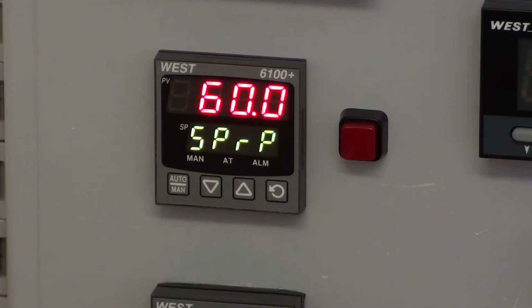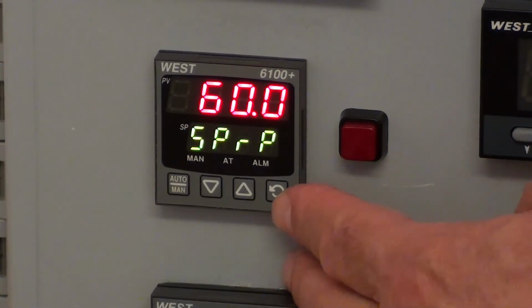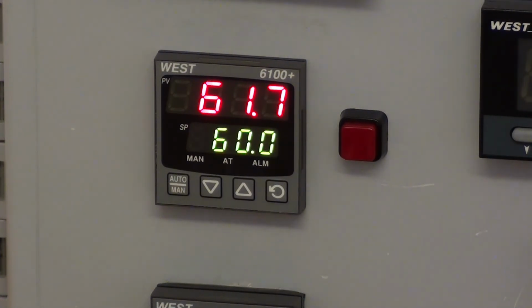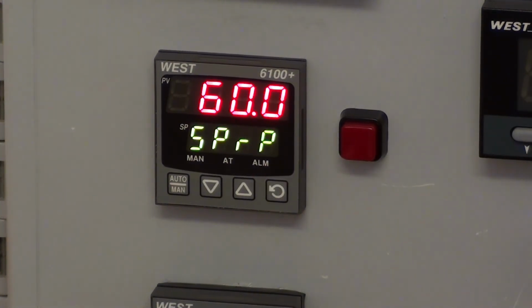The ramping set point has now reached the target set point of 60, and when it does that, it just stays there at the target value. So it will just stay at 60. If we have a look at the process, the process temperature is 61.8. So the overshoot is much, much better than we had with the previous example, without the ramping enabled. The set point ramping value stayed at 60 and will just stay there until that set point changes again.